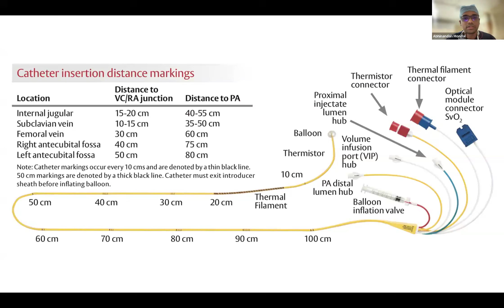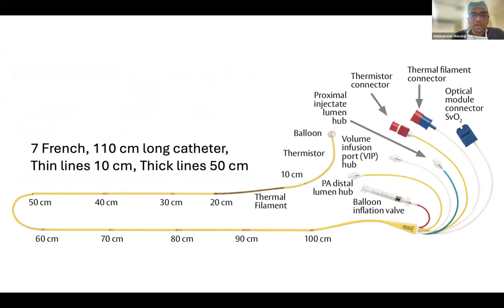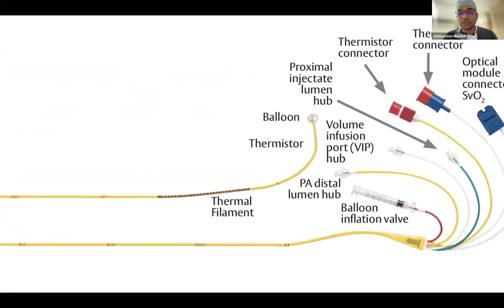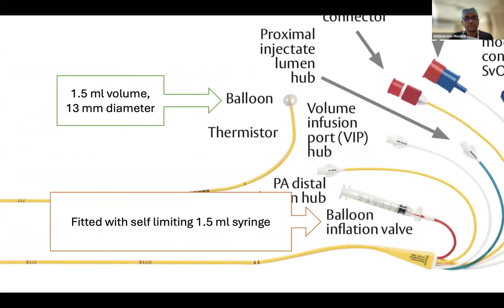We can see that this is a 110 centimeter long catheter. As we all know, it is 7 French. Thin lines are 10 centimeters apart and thick lines are 50 centimeters. These are all the same as our first and second generations. Moving forward, the tip has a balloon of 1.5 ml volume and 13 millimeter diameter, which has a balloon inflation valve, fitted with a self-limiting 1.5 ml syringe.